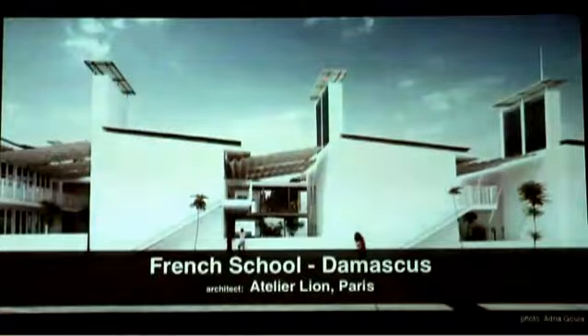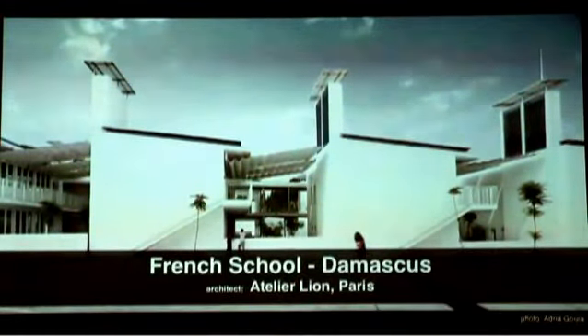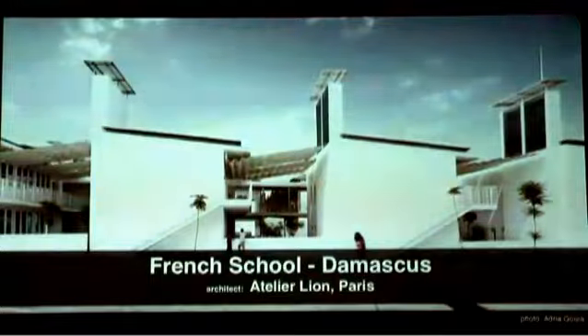So we ended up with these solar chimneys facing west. When the low sun in the afternoon hits the solar chimney, this back wall is a masonry black painted wall, and it absorbs the heat and stays hot at night. Damascus cools down at night quite significantly. So it pulls the cold air from these courtyards through pipes embedded in the ground slab into the classroom and then out through the solar chimney, cooling down the thermal mass of the building to provide good conditions the next day.